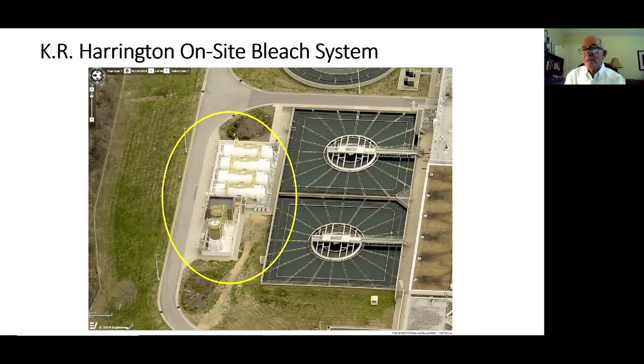It provides the ability to operate at full treatment capacity on generator power. It's not quite the same system here as at Omohundro, but we have totally updated switchgear and power controls, even a lot of the control boxes on equipment in the filter gallery and pipe galleries, utilizing sealed control boxes to prevent the level of damage that occurred during the flood.